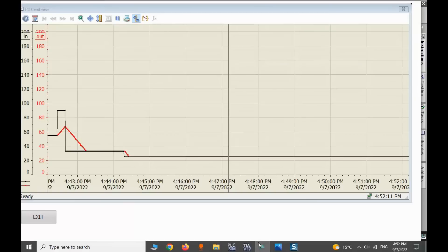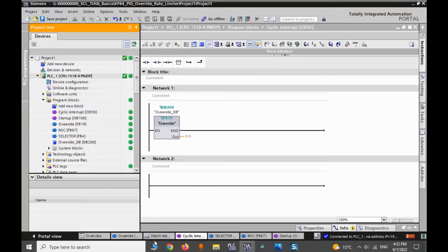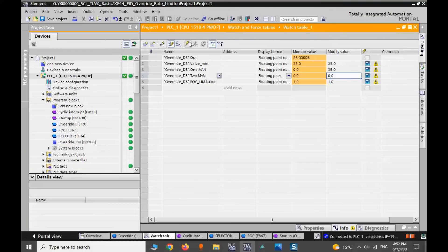We have the trend — we created the WinCC TIA Professional application to log these variables. So let us function test this. The minimum is 25, so we put the PID controllers in manual and increase the manual values — like 35. The PID output, PID1, is 35, so 35 will be the output.